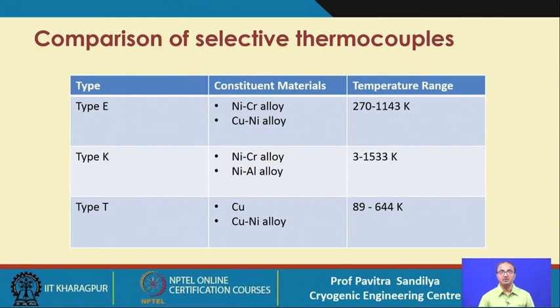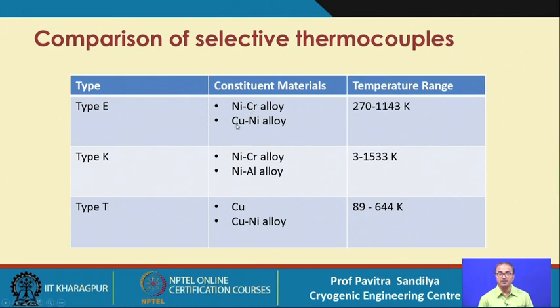There are different types of thermocouples depending on the materials chosen. Type E uses nickel-chromium alloy and copper-nickel alloy; type K uses nickel-chromium and nickel-aluminum; type T uses copper and copper-nickel alloy. All these thermocouples can operate at various temperature ranges depending on the material choice.